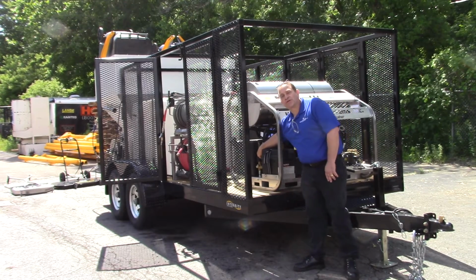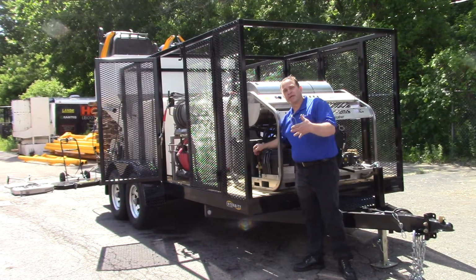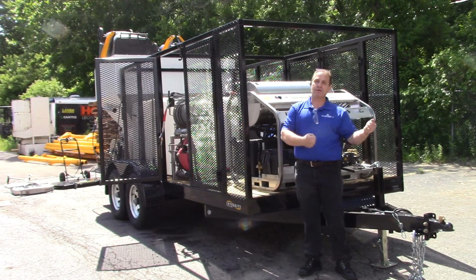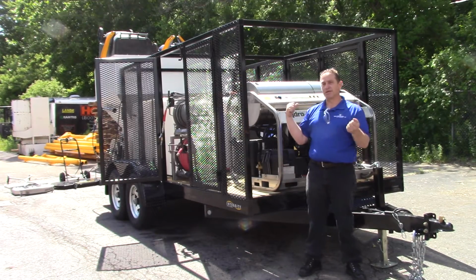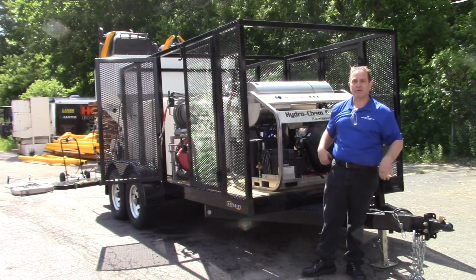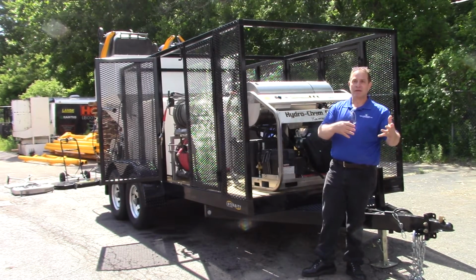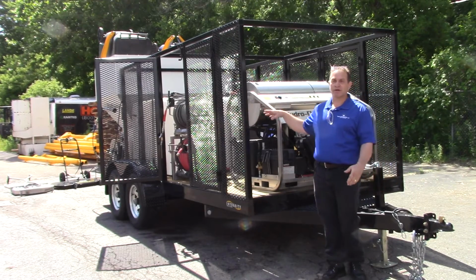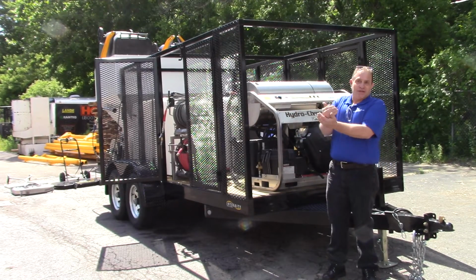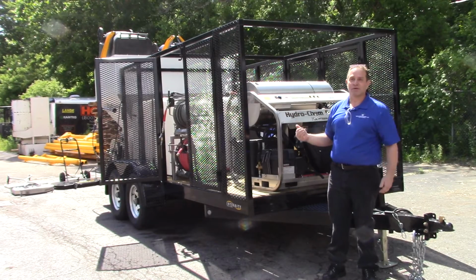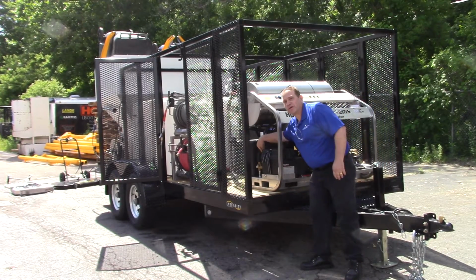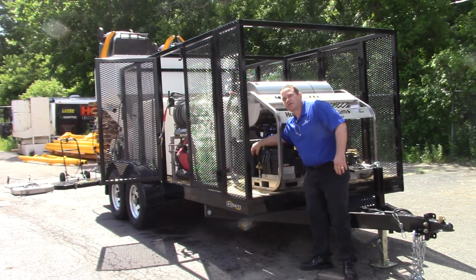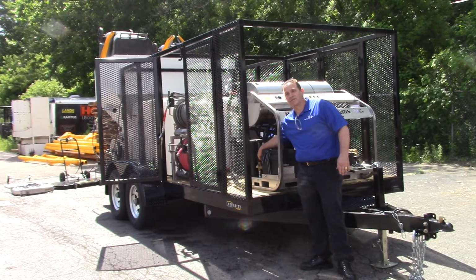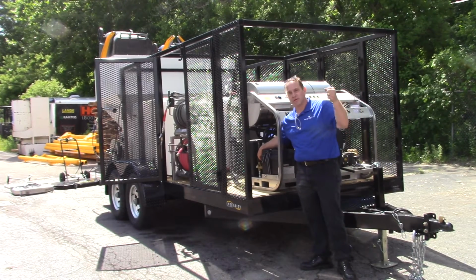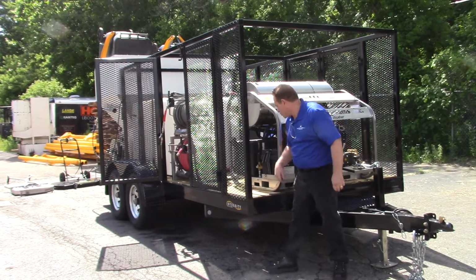You have a flow switch here that actually will kick on and off the burner based on the flow of water. So here you can even have the machine under pressure. Like this machine, if you shut the gun off, will stay at 3,500, 4,000 PSI in the line, even if you walk away, so the machine's running. So if it only had a pressure switch, it would think you needed it. You know, the burner would be on. So your flow switch here, kind of like a magnetic flow switch, that's where the one redundant safety device is. So without water flowing, no heat. You have a pressure switch.